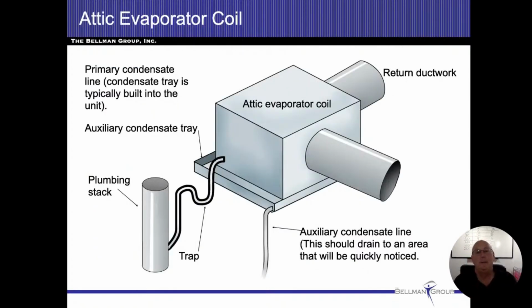All right. Now, if we're on the first floor or an attic install, we need to have a secondary means to protect against any sort of overflows or clogs that come into play. So if we're in an attic or anything other than a basement concrete floor, let's put it that way, so if I've got structure underneath us, we need to have some sort of protection. Even with a crawl space, you have to do that too.